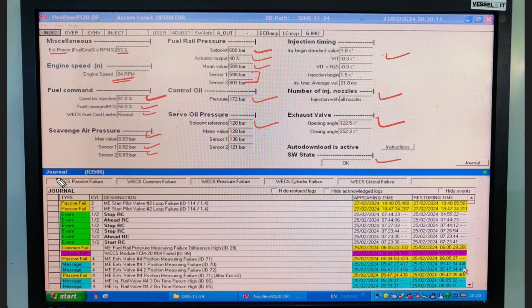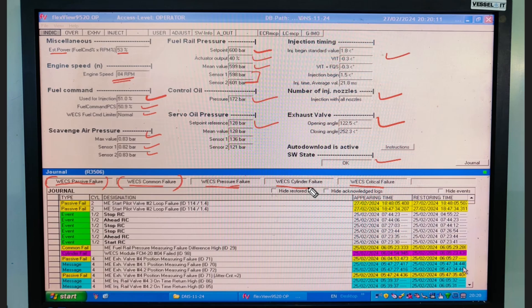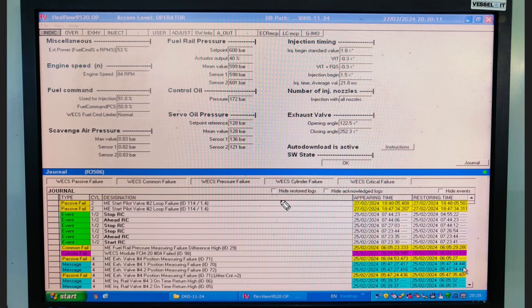Control oil pressure, injection timing parameters, nozzle injection, and exhaust valve auto download status are also shown. Below you can see the failure categories: WECS passive failure, WECS common failure, pressure failure, cylinder failure, and critical failure. When an alarm is triggered it goes into one of these categories - for example a loop failure goes to passive failure, a cylinder failure goes to the cylinder failure category. The color changes accordingly, and appearing time and restoring time are also shown.